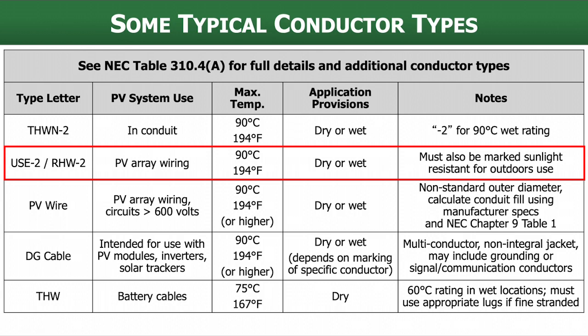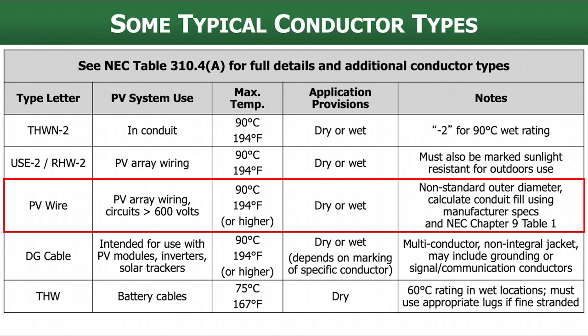Probably more common these days is PV wire itself. We use this for lots of array wiring, especially for circuits over 600 volts. PV wire is available up to 2000 volt rated, and it has a 90°C dry or wet rating. In some cases it has even higher temperature ratings beyond 90°C. It's available in a wide range of sizes, and sometimes it's used in conduit for PV output circuits from a combiner box. If you have a 1500-volt system, this is going to be the wire you can find with that voltage rating.